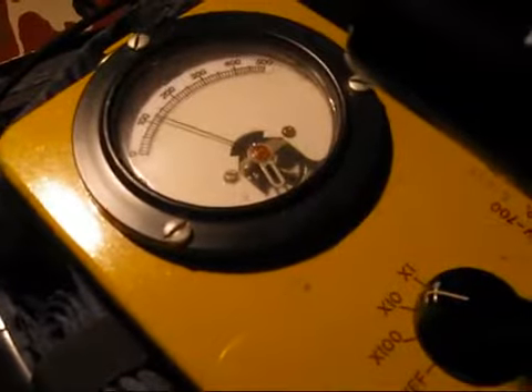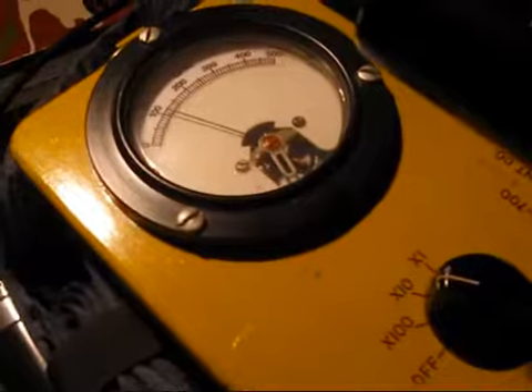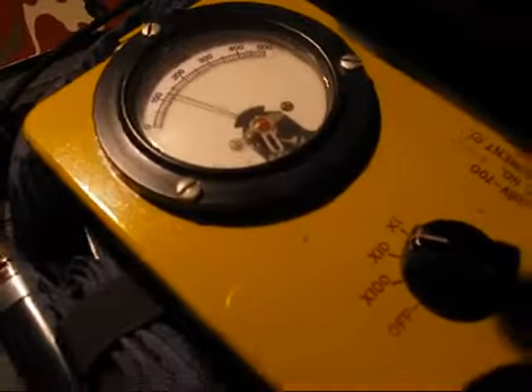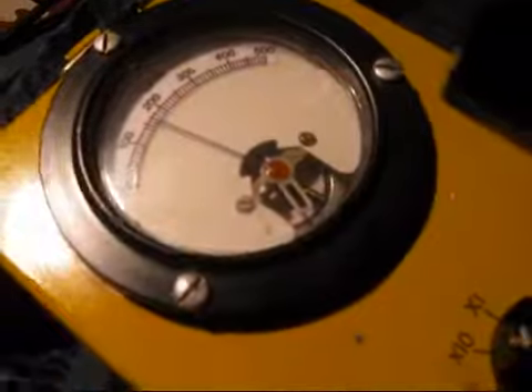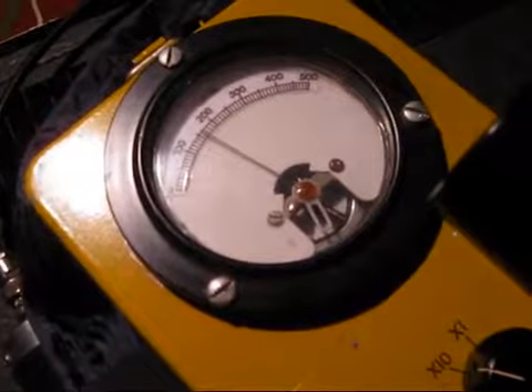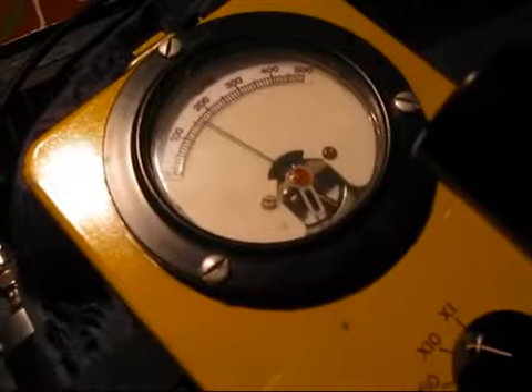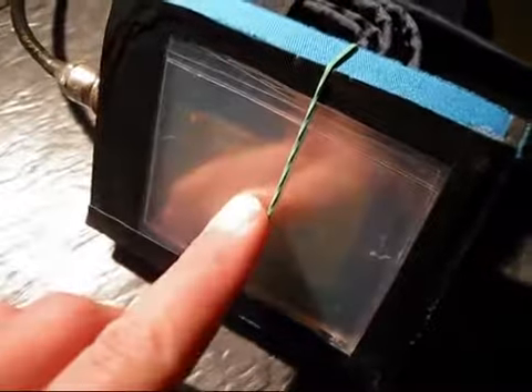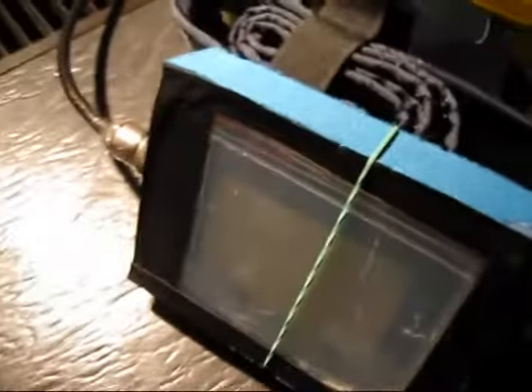So we can see we have like 1,000 to 1,500 counts per minute of background radiation. Now the strontium-90. Well, that doesn't do much, does it? Just slightly over 1,500. That's because this type of detector cannot register anything but gamma and X radiation. So I'm just using the pancake probe again with the aluminum shield in place, because well, that sodium iodide scintillation counter is shielded as well.